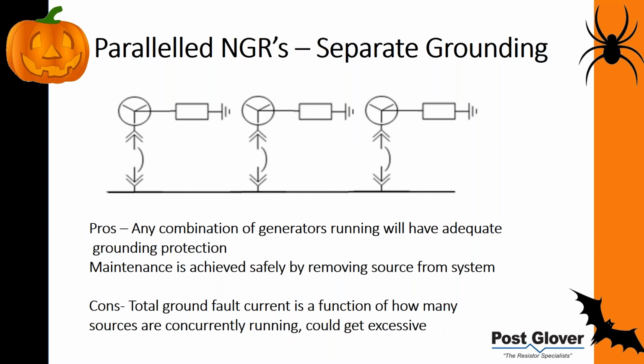So you have a resistor at each and every source, paralleled. That is one option—it's called separate grounding. We like this method, there's a lot of benefits to it. It depends—if there's a lot of generators, it may not be practical, because one of the issues with this method is that your ground fault current is additive.